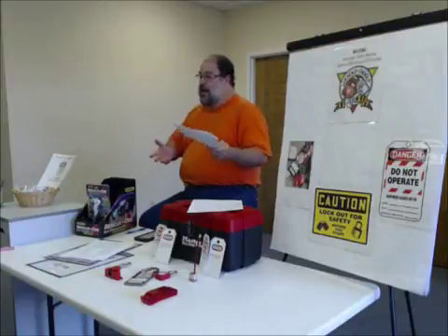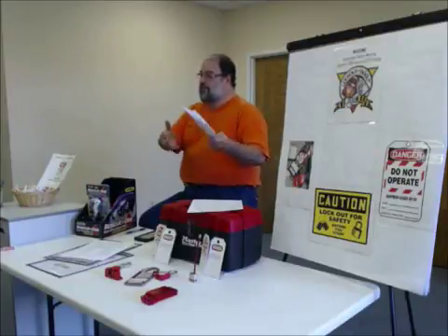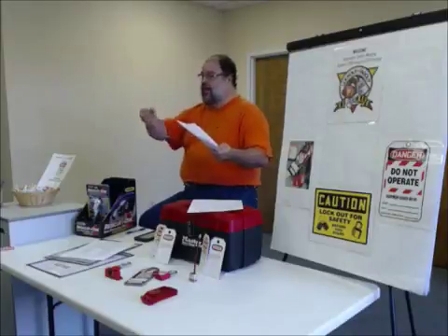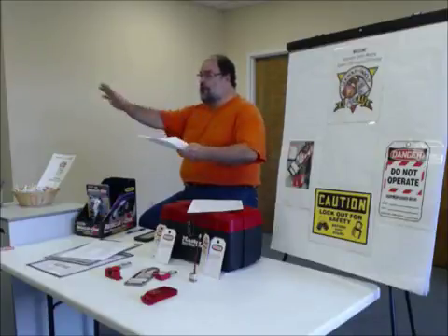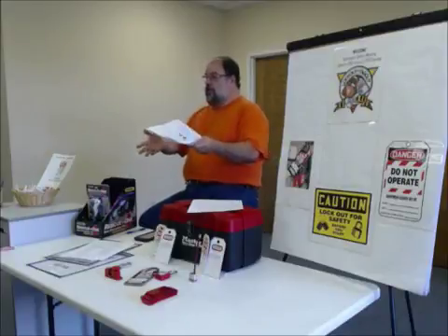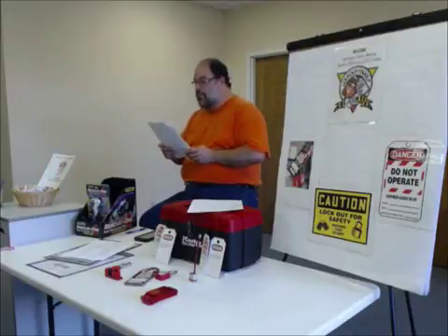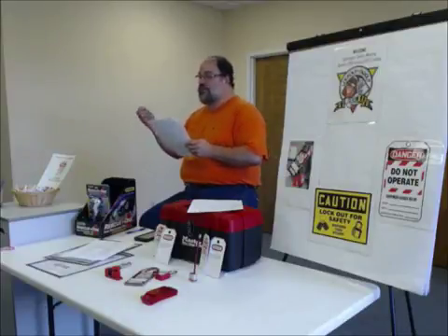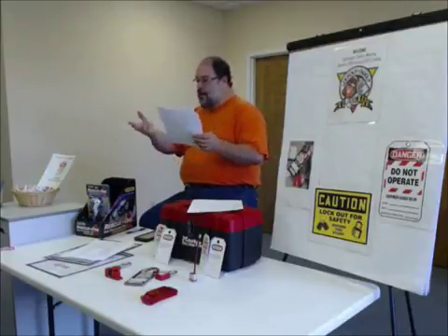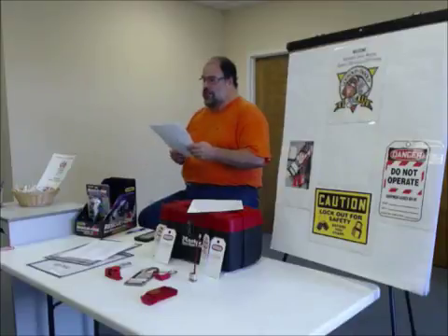Because for 3 hours or 6 hours or 3 days, this equipment has been out of service, and people got it in their head it's safe to walk through here because this is de-energized, it's not operating. Now all of a sudden, it's no longer safe, so you have to keep checking to make sure nobody's in harm's way. If necessary, sound the horn or the alarm. Like on the paint line, we have a bell that we sound that lets everybody know that we're fixing to start the line up. Next, you attempt to cycle the equipment.